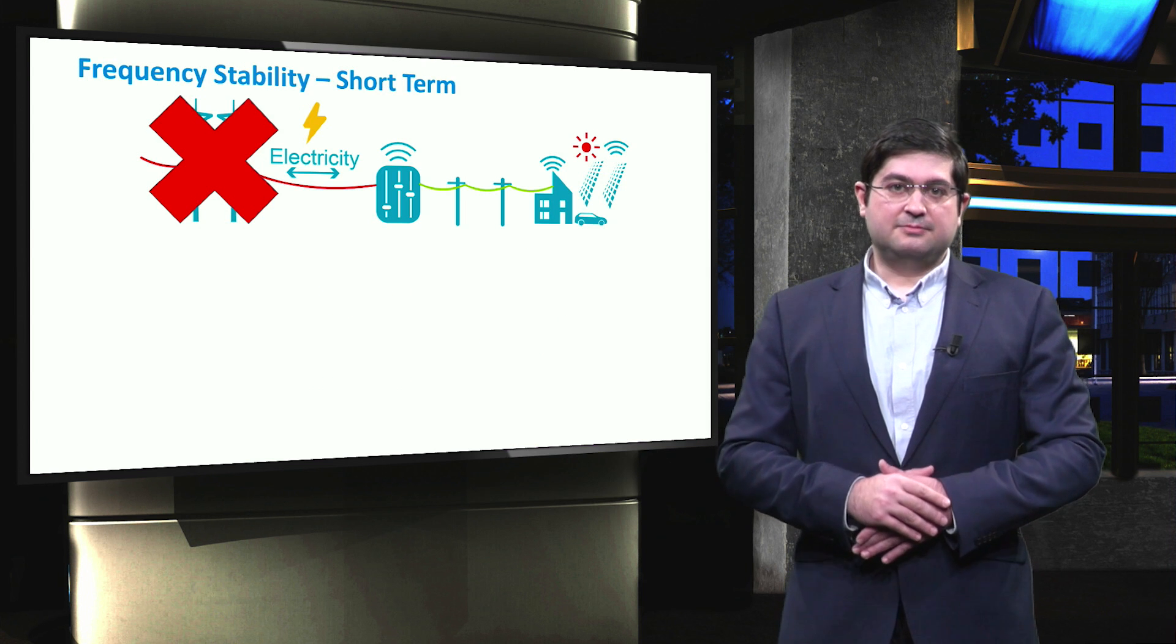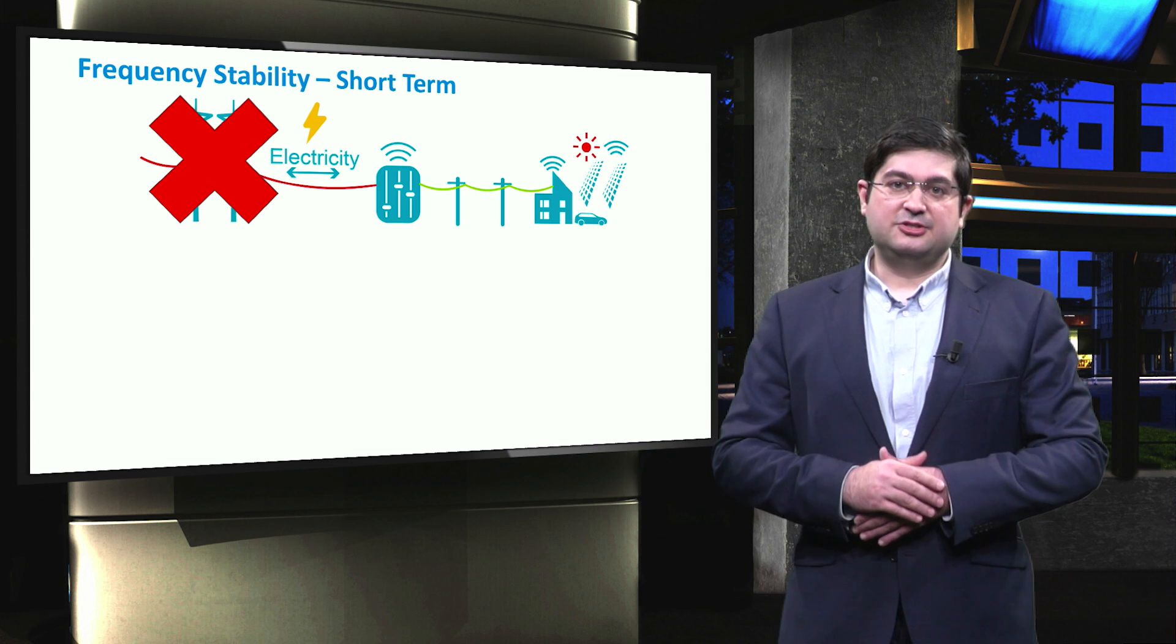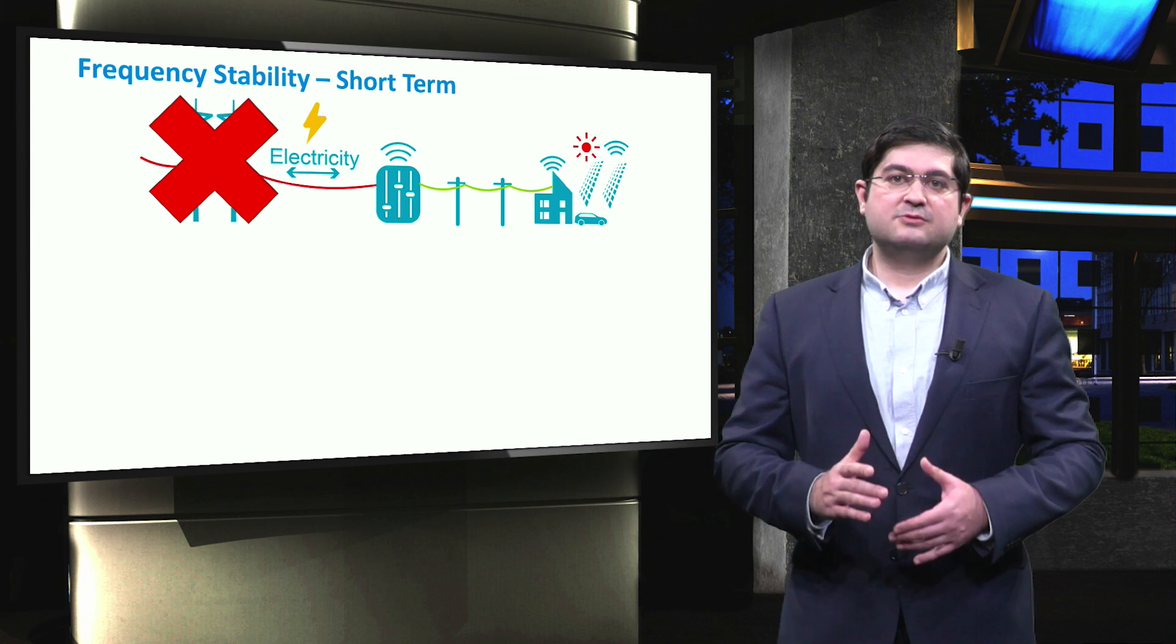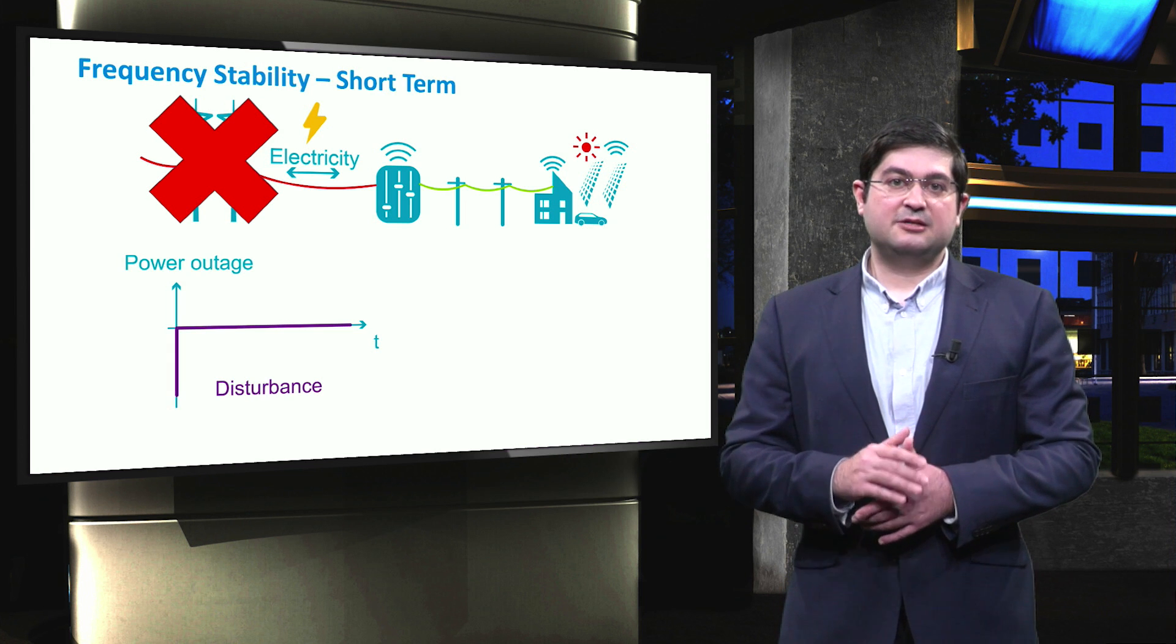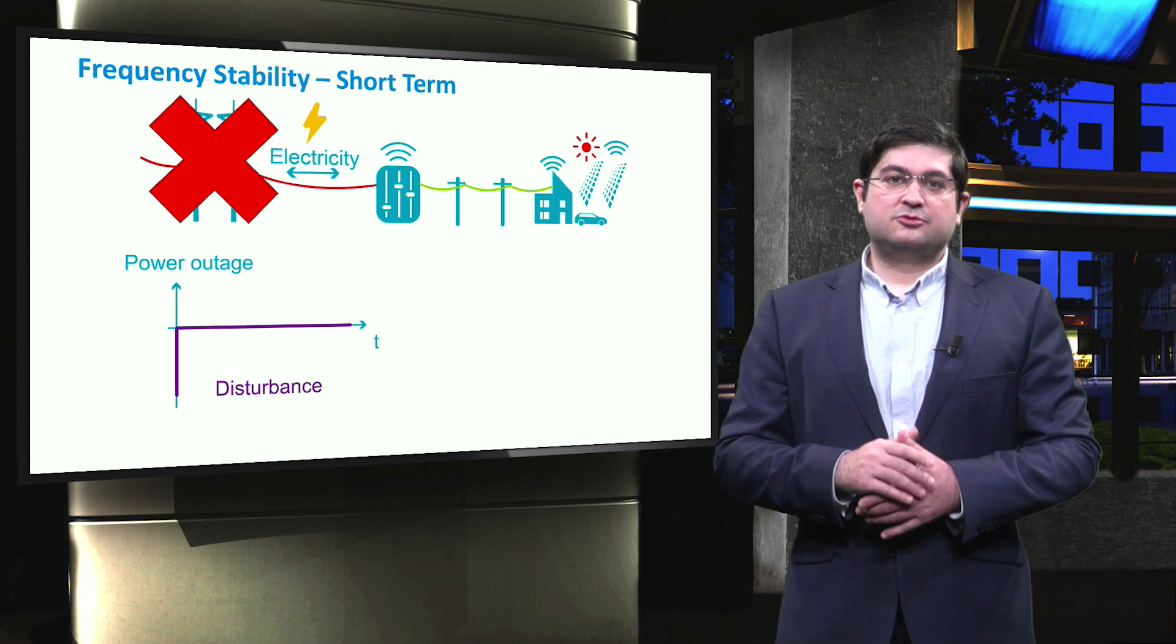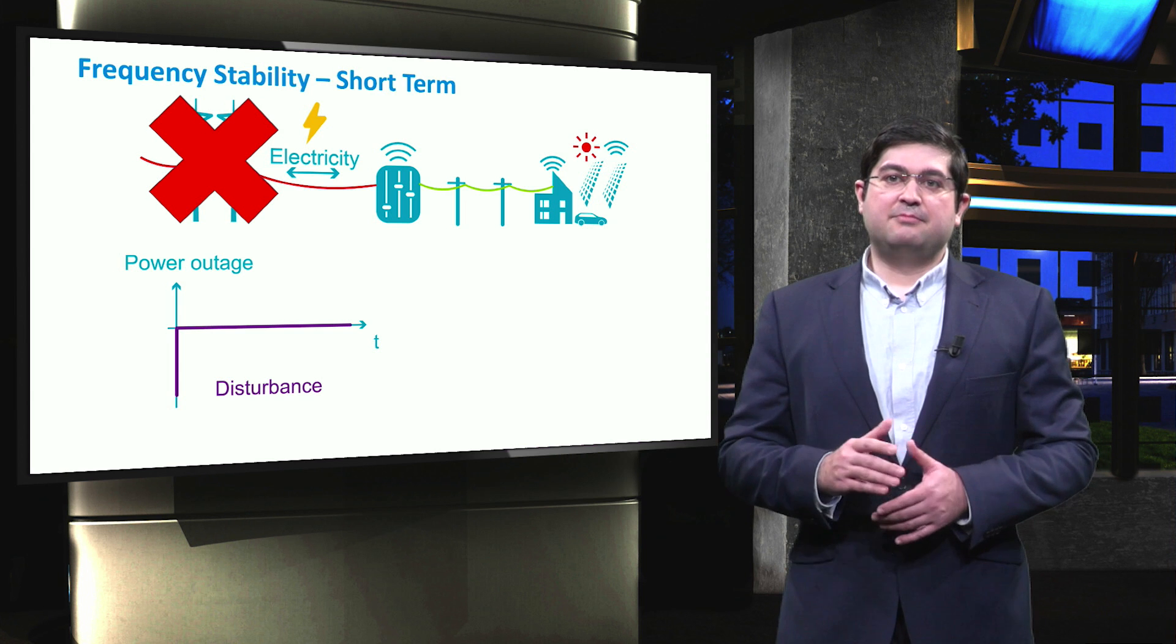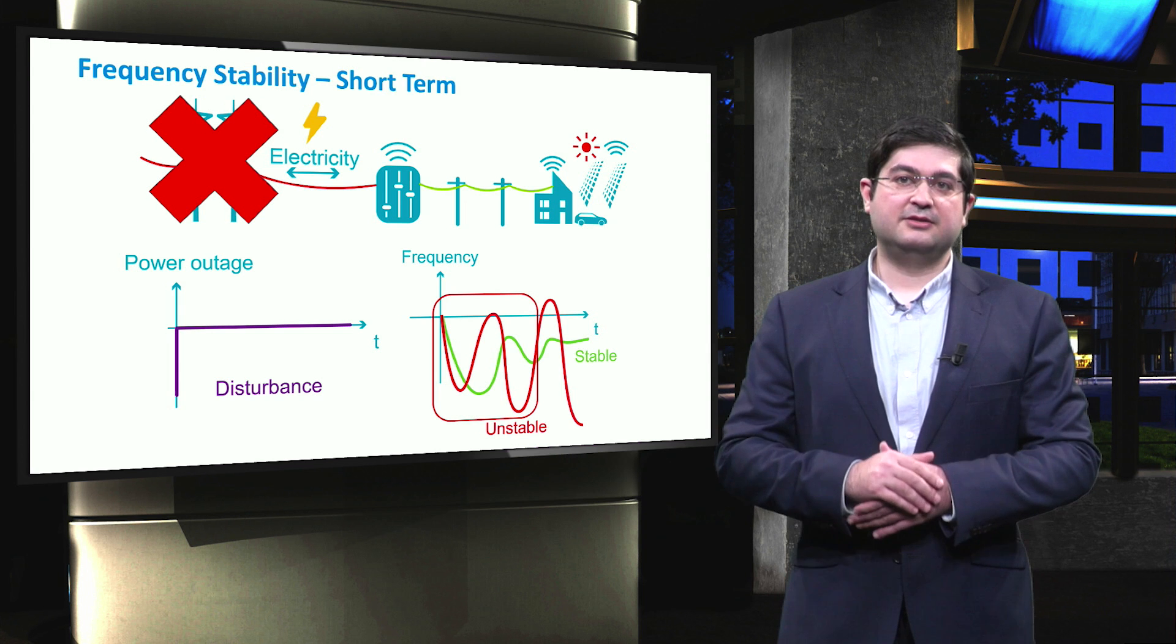During the islanded mode, maintaining the stability of frequency in microgrid is a very challenging task. In the first place, we describe primary frequency control, which is responsible for continuously adjusting the frequency variations, which occur due to disturbances like power outages. Note that this control is automatically and locally activated by the so-called droop control of DG units in microgrids to arrest the initial frequency drop right after a contingency event.